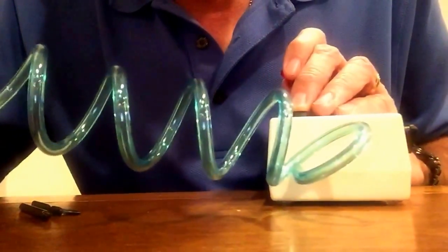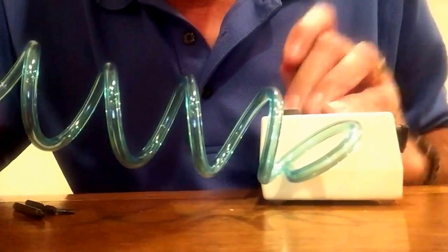At this time we're going to take the brush. We're just going to give it a little brush to kind of loosen up any particles that might be on the holes that we're getting ready to clean. Once we've done that, we'll take the Jodi-Vac and we'll turn it on. It makes a lot of noise, so I'm going to do it with it off just to show you what you do. You turn the Jodi-Vac on and you very gently put it into the hole where the filter was. Kind of rotate it around, maybe move the hearing aid a little bit. You visually look at the hole, and the idea is to get any visual earwax out of the hole.